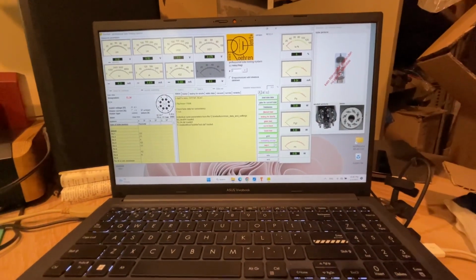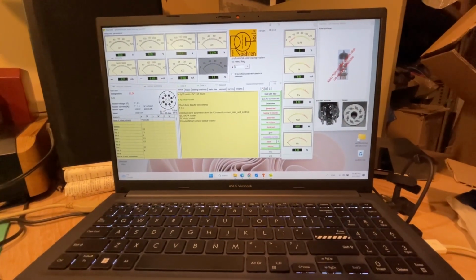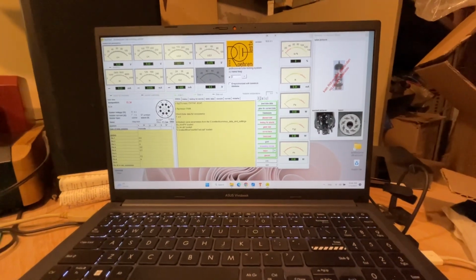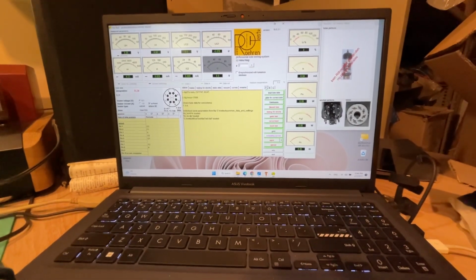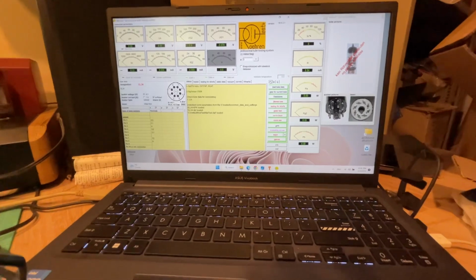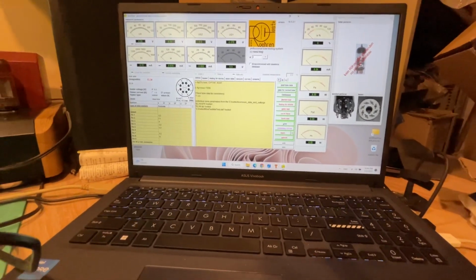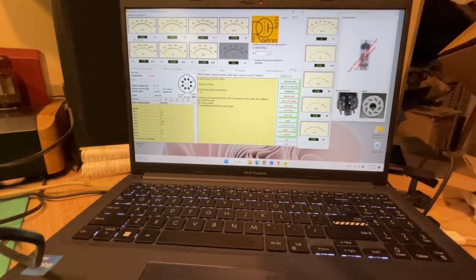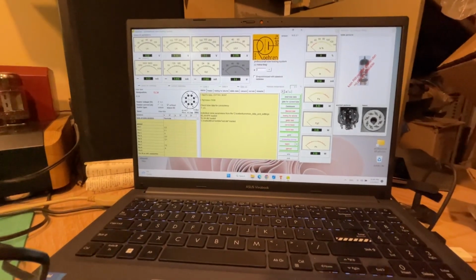We only need to insert the next tube, and the tube tester saves the data, makes all the tests, and makes a sound when it's time to change the tube. It sings, we insert another tube, it detects it and starts the test automatically. Only changing the tube, no clicks, no other operation needed.